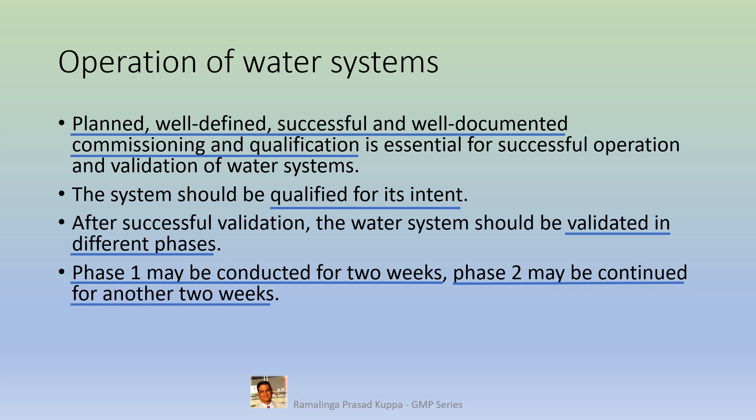During this phase, as per a defined plan, chemical and microbial testing should be done. Continuously monitoring the incoming feed water daily to verify its quality, and continuously monitoring after each step in the purification process, at each point of use and other defined sample points.